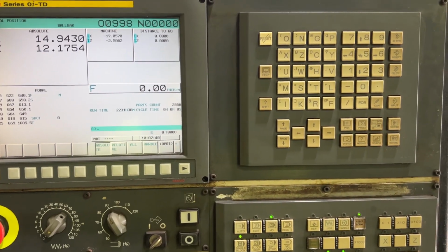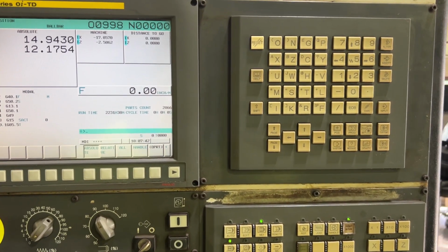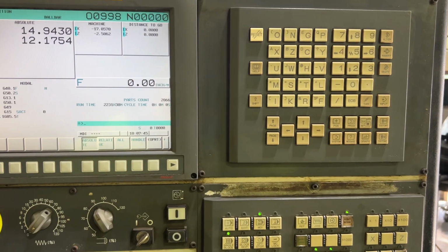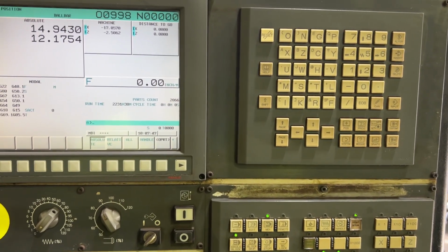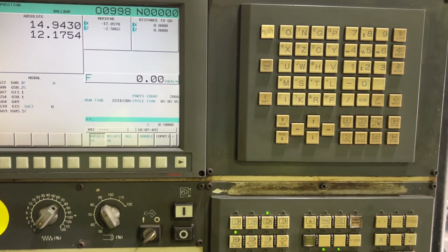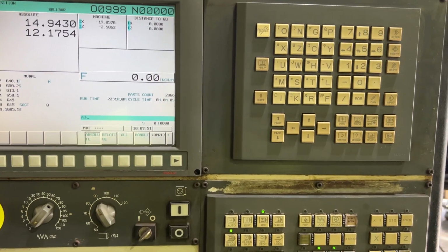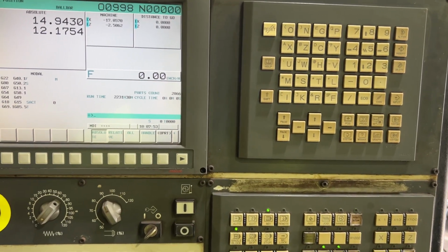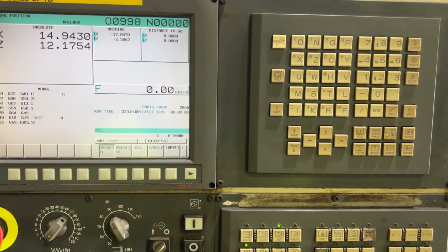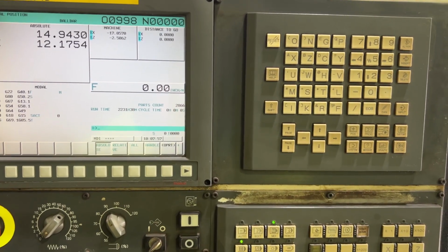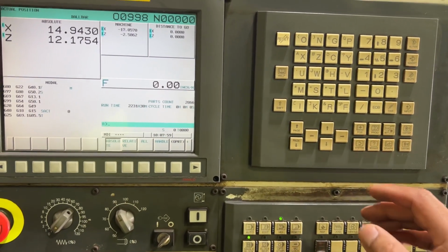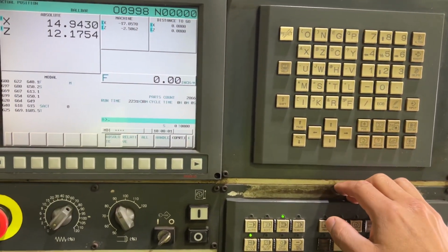On this machine with the Fanuc series 0i-TD CNC, we're going to see how to replace an output that is burned. The output is always on, but we don't have an output module to replace, so we're going to use an output that is spare right now, and we are using logic to replace the original one.